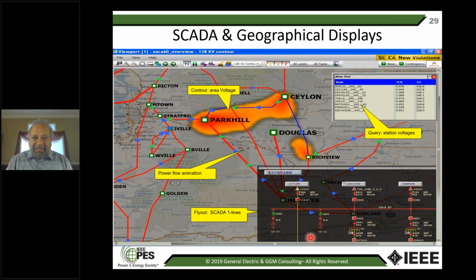This is your typical SCADA display, which has been in existence for 50 years. The little red squares are circuit breakers. From the SCADA display, an operator can open or close a circuit breaker through a multi-step procedure: you select, say what you want to do, and then execute. You want a multi-step procedure so you don't inadvertently open or close the circuit breaker.